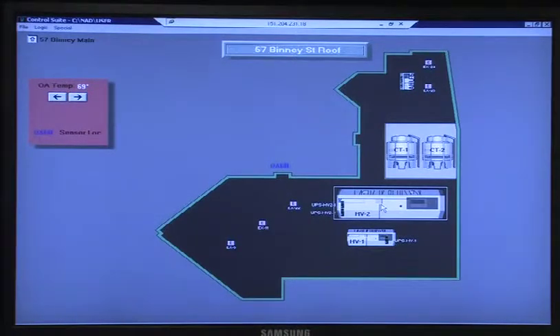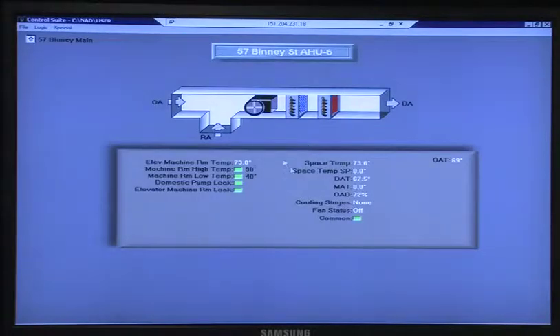So when the unit's running, it's ventilating through. Whether or not that ever shuts off, and if it shuts off, you know what happens. But in the summertime, I can't imagine that thing ever shutting off. No, it's just to maintain the UPS system so they don't heat. I can't imagine that thing ever shutting down. So if that happens, we'll address it. That one definitely. This stairwell pressurization is always off, other than the fire command, and it has components in there that have to stay cool. So we knew that. These here, like I said before, are the elevator machine room unit. That's a Trane unit doing the elevator machine room.